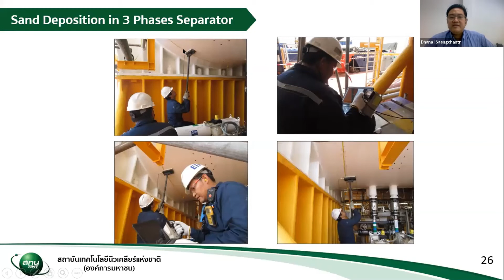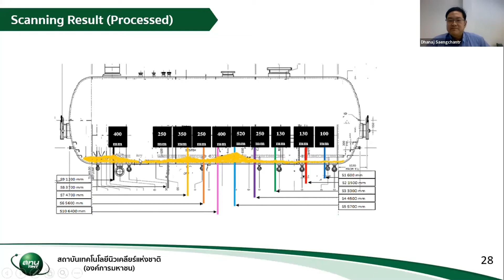We use a measuring tape and just move the probe along the periphery of the tank and make a count. Finally, this is an example of the plot, scanning line number 10. We can see the interface between the air and the liquid inside, and this is the deposition. With all this data, we can make a picture and tell the plant that this phenomenon is occurring in their vessel.